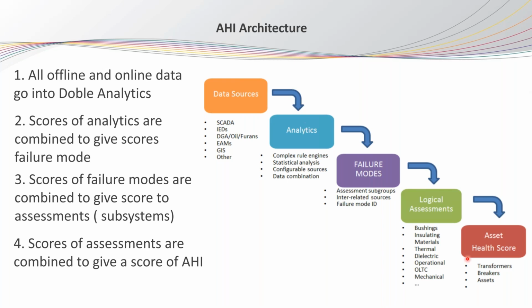In another way, if we look here, we have a transformer. We divide it into a number of subsystems, and for each subsystem, we define the related failure modes, and for each failure mode, we have the source of the data. It can be online or offline, etc. These data will go through analytics, and these analytics are built according to the latest standards. They will convert the values of these data into scores. Each group of scores will combine together to give only one value for each failure mode. The scores of each group of failure modes will combine together to give a score for each subsystem. And finally, the scores of all subsystems will combine to give you the health index score.